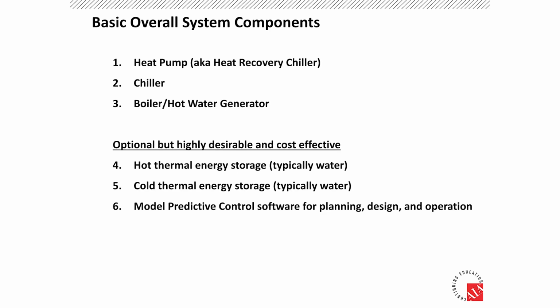The basic overall components of a system for any building or collection of buildings for clean electrification are a heat pump or heat recovery chiller, and chillers and boilers or hot water generators to handle the margins you can't meet with heat recovery. You can also use ground source heat exchange and other things, though you don't have to. If you want to make the system even more efficient and cost effective, add hot and cold thermal energy storage.